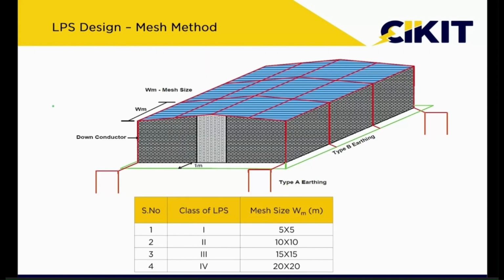The second method is the mesh method. In this mesh method, we will be laying the conductors in the form of a mesh over the structure to be protected. Again, here the spacing between the conductors depends upon the levels of protection. For level 1, we will be going for 5 by 5. For level 4, we will be going for 20 by 20. But we normally won't use this method for the oil tanks. But we can use this method for any other structures like control rooms, security rooms, and other administrative blocks in these oil refinery plants.